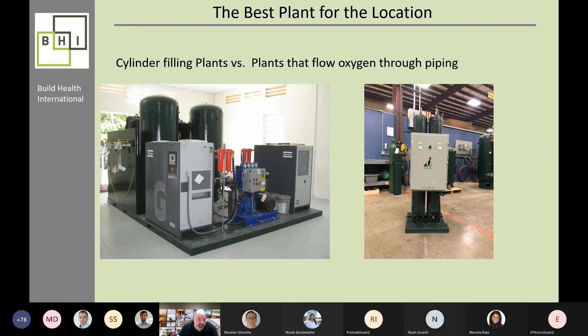But if you have piped oxygen, you don't necessarily need to fill cylinders. And the blue compressor you see in this photo is a high pressure cylinder filler, which is in many ways the Achilles heel of the PSA plant. It is very expensive. It requires frequent maintenance and very expensive parts. So one thing to consider is, do you need to fill cylinders, and if so, how many? One of the trends we're seeing and really pushing is, wherever possible, to flow oxygen at a low pressure through piping and not fill a lot of cylinders, just fill enough cylinders to serve as a backup. Next slide, please.